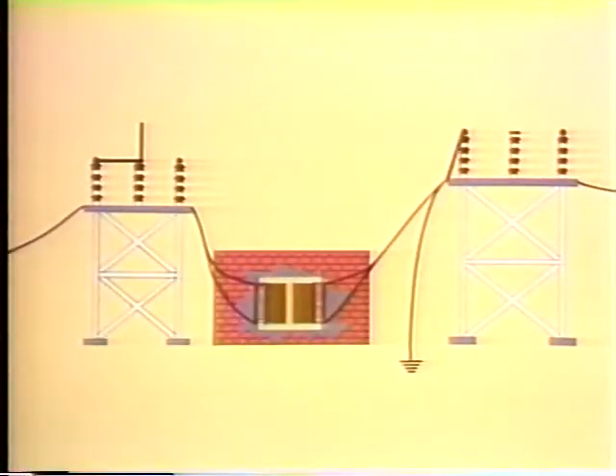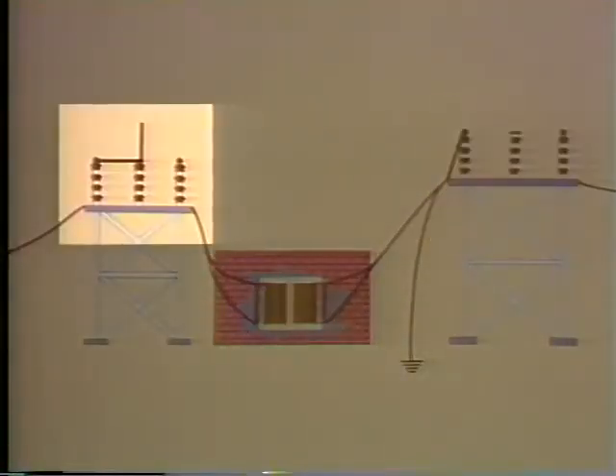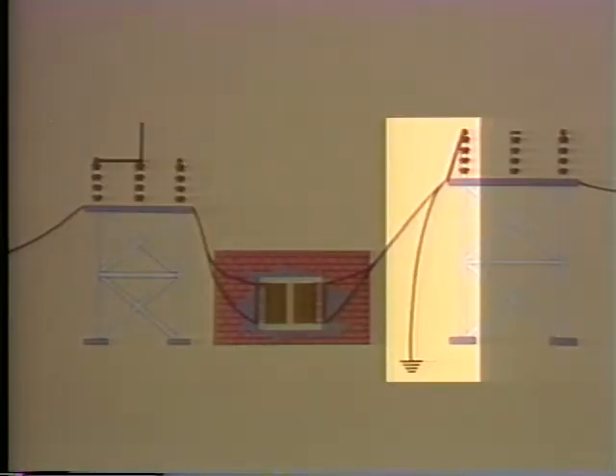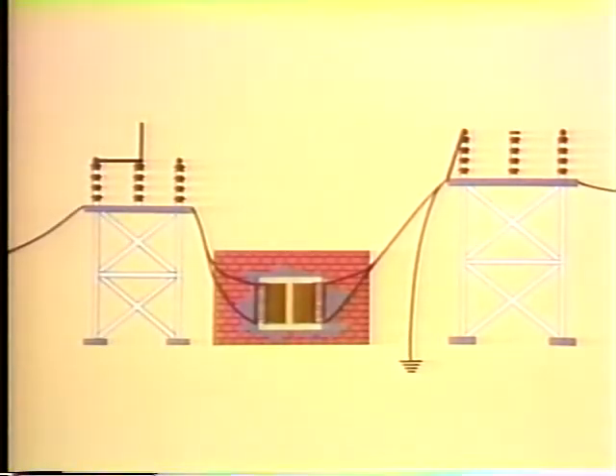Here's what the situation looks like now. Open breakers and disconnects isolate the unit on both the primary and secondary sides. In addition, the primary is grounded. After making routine checks for voltage, he can work on the primary without risking a shock from induced voltage. Proper switching and grounding are the real keys to making maintenance of high voltage equipment as safe as possible.